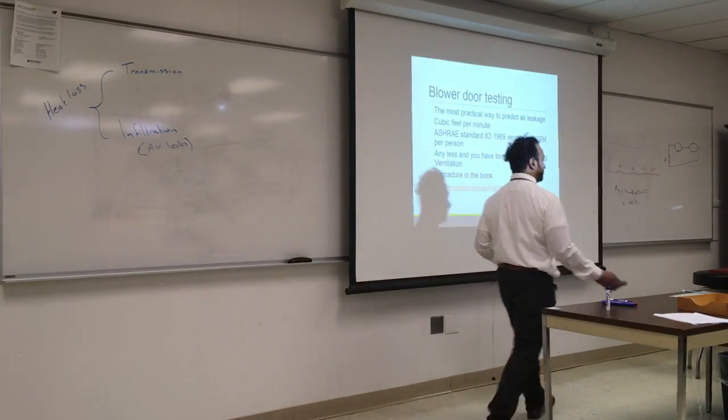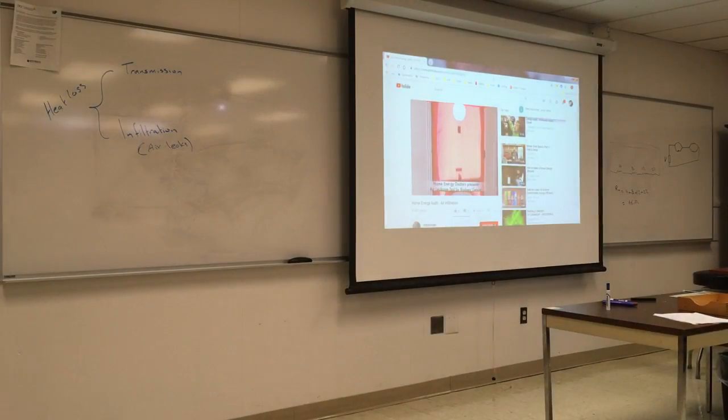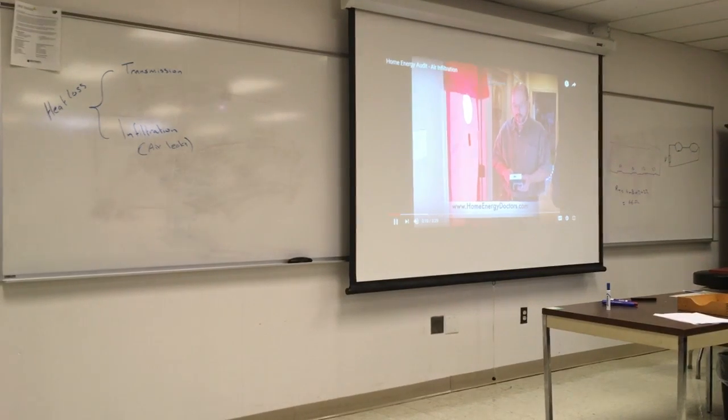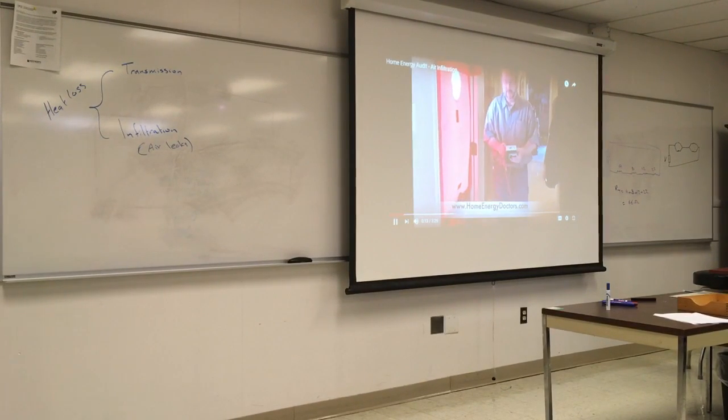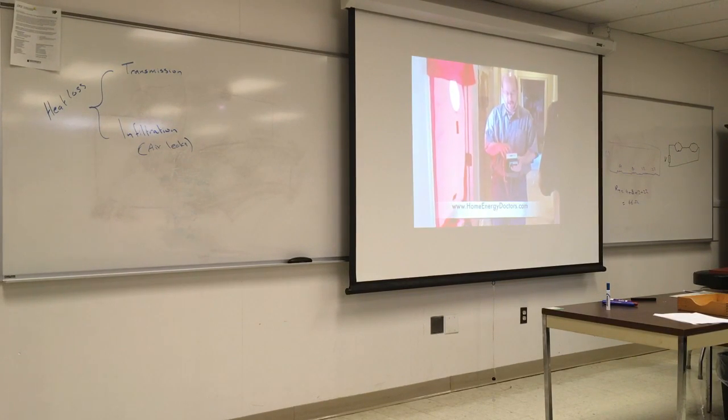There is a procedure in the book for blower door testing where I will show you a video. I'm sure there are a lot of videos online you can watch about this. We're testing for air leakage using our blower door work. We're going to turn this on. We'll stand in front of the fan. It's going to get a little noisy. Depressurizing the house, 50 pascals of air.